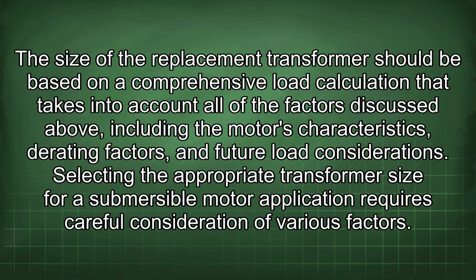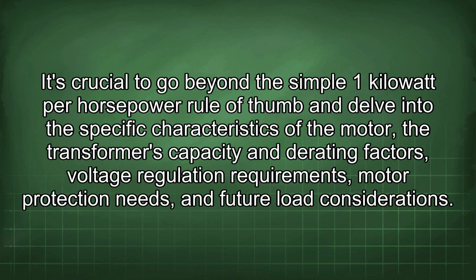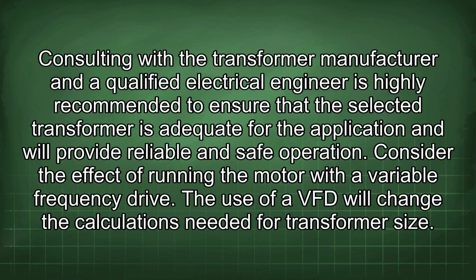The size of the replacement transformer should be based on a comprehensive load calculation that takes into account all of the factors discussed above, including the motor's characteristics, derating factors, and future load considerations. Selecting the appropriate transformer size for a submersible motor application requires careful consideration of various factors. It's crucial to go beyond the simple 1 kW per horsepower rule of thumb and delve into the specific characteristics of the motor, the transformer's capacity and derating factors, voltage regulation requirements, motor protection needs, and future load considerations. Consulting with the transformer manufacturer and a qualified electrical engineer is highly recommended to ensure that the selected transformer is adequate for the application and will provide reliable and safe operation.